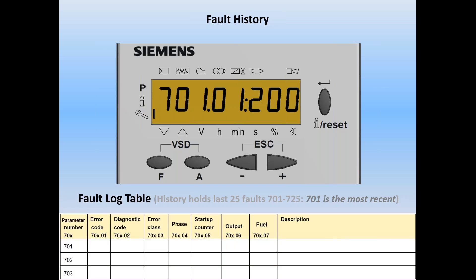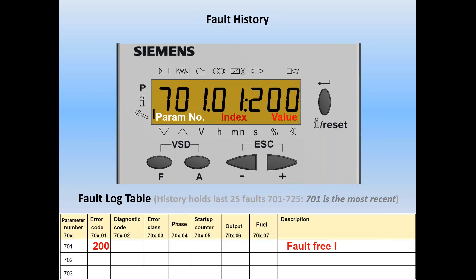On your screen you'll see three sections: the parameter number, the index (in this case 01), and the value of that parameter and index — in this case 200. We enter 200 into row 701, column 01. When we look that up in the book, fault code 200 is ironically 'no fault,' which just tells us the burner is fault-free at the moment.